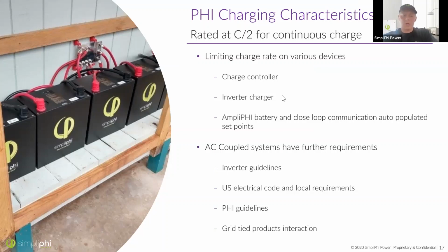Whereas inverter chargers, you definitely have the ability to program some of them to reduce the charge rate, though not all have this capability. And I would argue that depending on the layout of your system, if you've got an AC coupled PV array, some of the inverter chargers just are not reliable in actually following the programming that you've put into the charge rate. So I would say it's highly dependent on your equipment as far as how much you can trust that charge rate. Easiest way to do it here is to just use a battery bank that's sized to handle the maximum charging current of that inverter, or use an AmpliPHI battery with a communicating device.